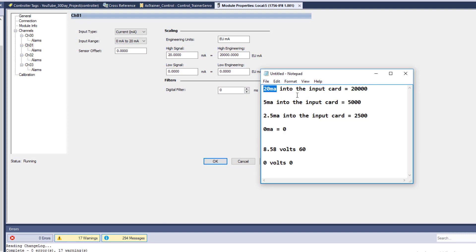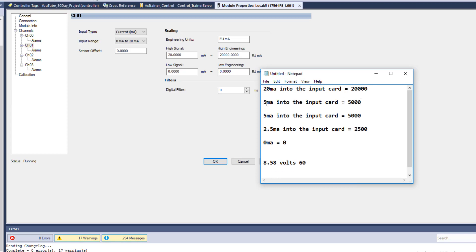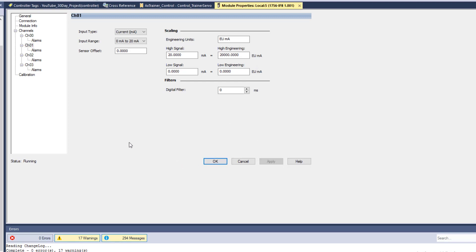So if I had 20 milliamps into the input card it would equal 20,000. If I had 5 milliamps it would equal 5,000. If I had 2.5 milliamps it's going to be 2,500. If I had zero milliamps it's going to be zero. And if I had 10 milliamps, you can easily tell that's going to be 10,000. That's the scaling and how it would be used.